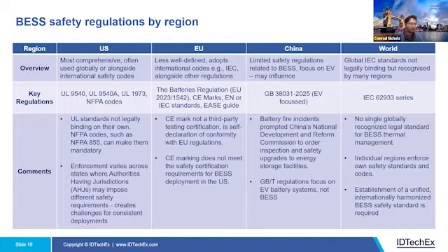Overall, current safety standards may not be sufficient for large-scale modern BESS deployments. As capacity of battery systems scale, along with the size of BESS deployments, so do the risks of thermal runaway. Current safety testing and regulatory frameworks like UL 9540A may not be sufficient to ensure safe BESS deployments and installations.